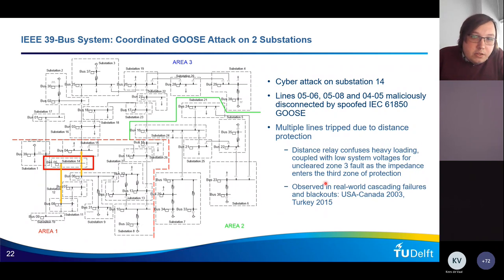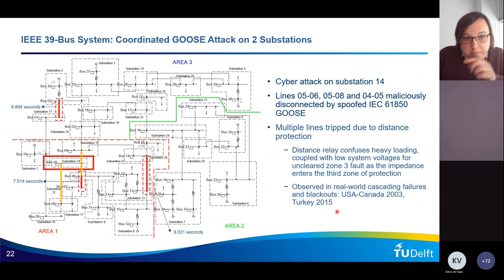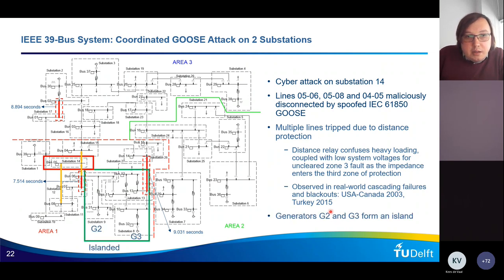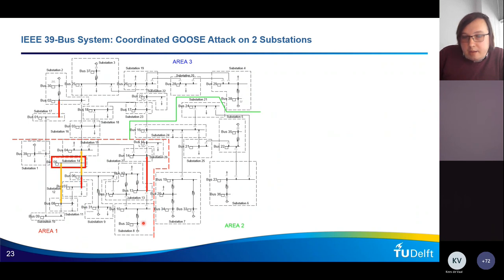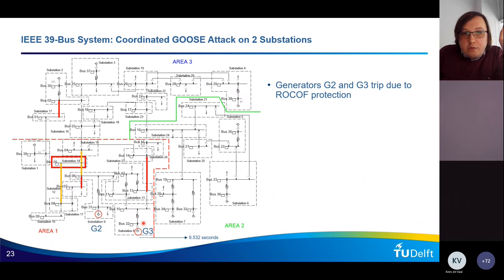And this phenomenon was observed in real-world cascading failures and blackouts, like in United States 2003 and in Turkey 2015. So for this reason, multiple lines are disconnected from the power grid, causing this area to island. So we want to avoid islanding. So the generators 2 and 3 will be isolated. And their rate of change of frequency, the ROCOF protection, will disconnect these generators to avoid damage to the turbines, but also for safety reasons.